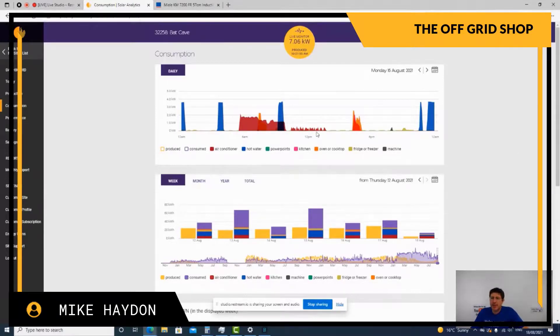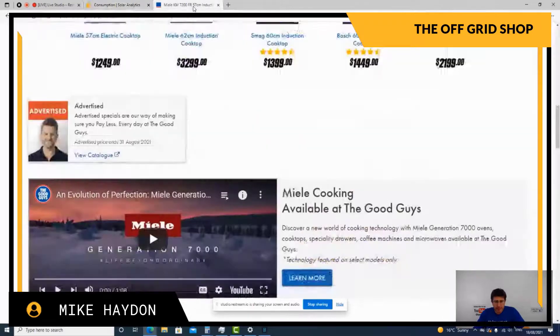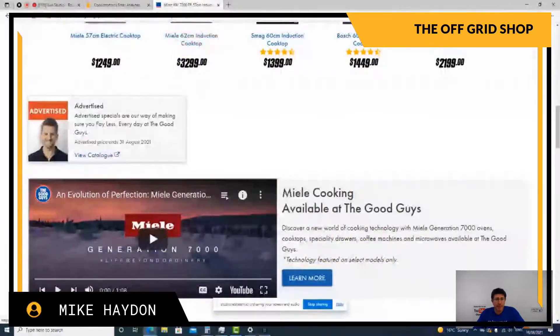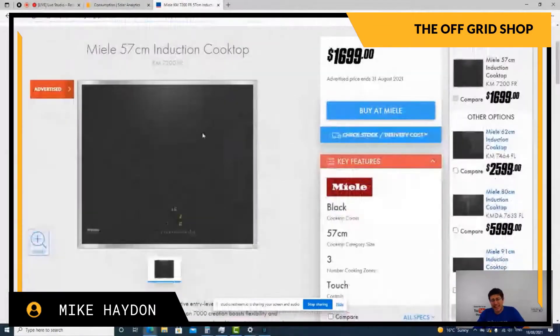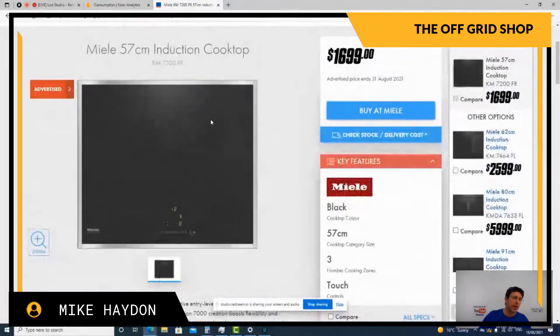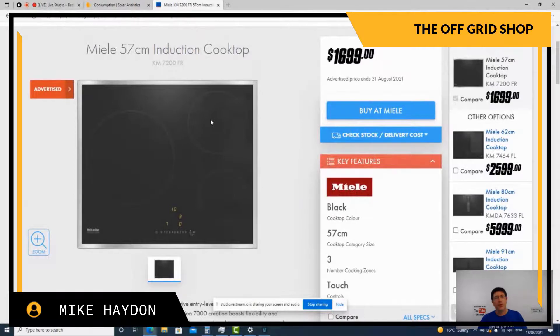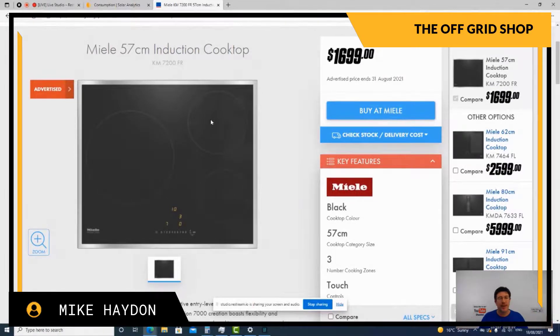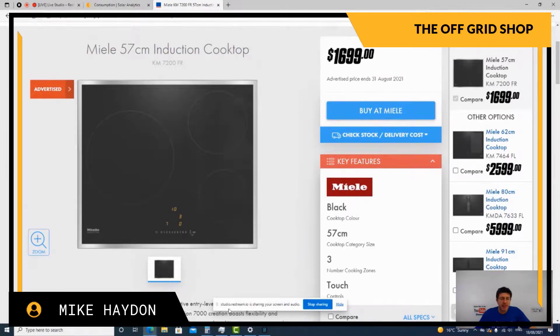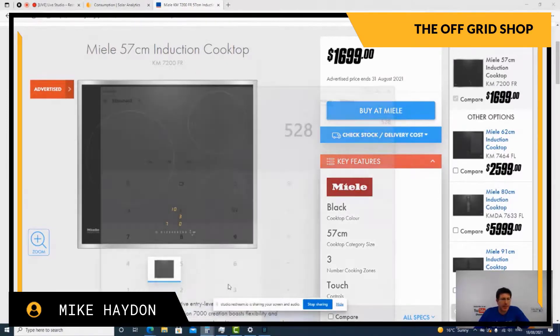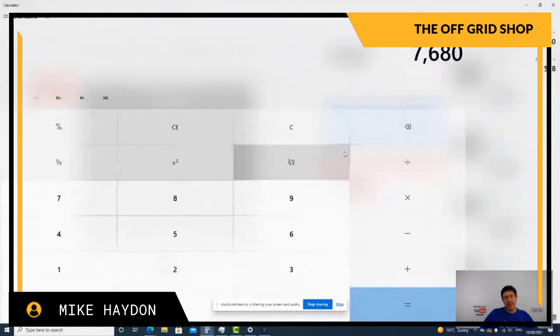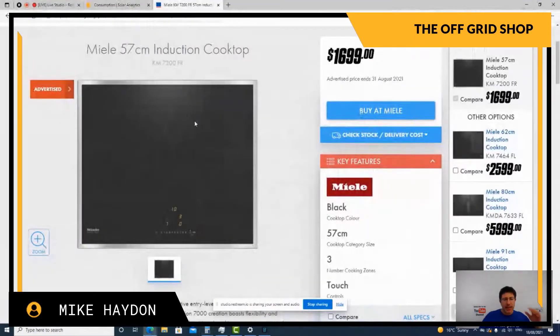So yeah, guys, I hope this has been helpful with cooking and thinking about sizing your inverter and what your appliances can do. It's really hard when buying this sort of stuff from Harvey Norman, the Good Guys and stuff like that, getting the exact appliances. A lot of the specifications pretty much say it's a 32 amp breaker that's got to go onto it, or a 20 amp breaker to a brandy cooktop, things like that, that actually really doesn't say how much energy it pulls at any one time. And if that's what it says, it's pretty much the easiest way to do it is all you do. If it does say 32 amp breaker, 32 times 240, your voltage. So it's 7.6 kilowatts. So you just times your volts times your amps, that's going to give you the watts of what size that you're going to require.